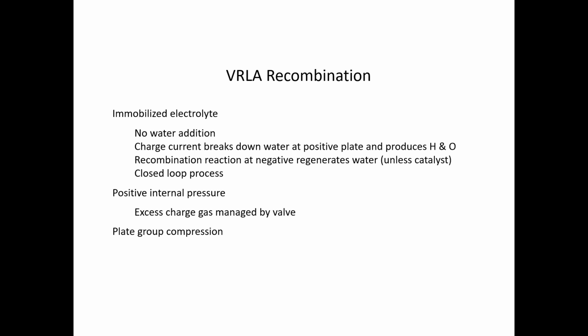But at the very basic level, what happens is the electrolyte is broken down. Hydrogen and oxygen are the end result of the charge process. They're broken down on the positive. The hydrogen and oxygen recombine because we have that pressure relief valve on it. It's forced to recombine, and it recombines on the negative. Now that's good. The idea is we're limiting water loss. We don't have to add water to the batteries.